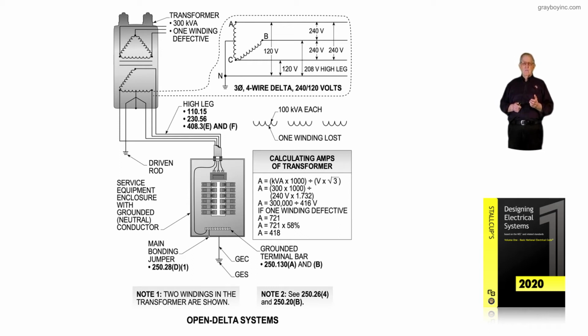But here we're using 3 transformers to obtain our amps, not 2, as we'll see there. Now, if one winding becomes defective and fails in some way, then the 721 amps that you would obtain if all 3 transformers were active and operating properly, we would take 58% of 721 and we could reduce that load from 721 down to 418, and the loads that were essential to the system we could supply until we obtained another transformer to reconnect, say, into a delta hookup, so that it was closed. So we would just order 100 kVA and reconnect it, and then we could get a full 721, and the 418 we would no longer have to worry about.